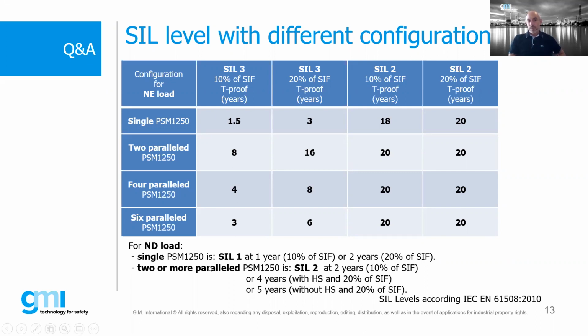There is an example also for normal de-energized load here now, and I see that for a single power supply, there is just a value for SIL 1, 1 year or 2 years, with 10%, 20% of the SIF. Two or more in parallel is valid for SIL 2 at 2 years for 10% of the SIF, for 4 years with the HS, this time the hot swapping, and 20% of the SIF. So more devices increase safety and also increase availability, especially on normal de-energized.